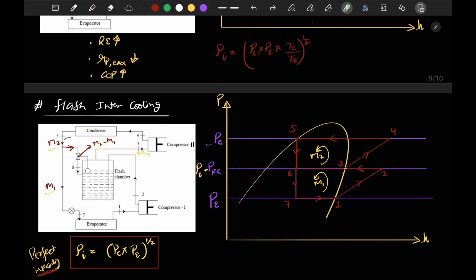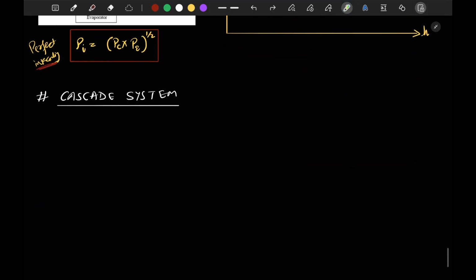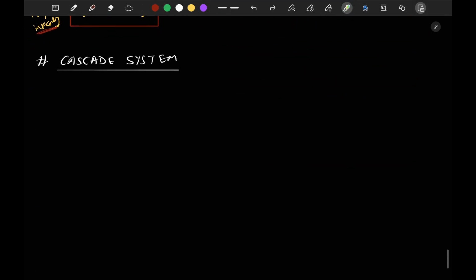Similarly, extremely low pressure in the evaporator will lead to high suction vacuum. So these are certain problems which arise in operation with a single refrigerant, in case of our high pressure issue. So for that case we use our cascade refrigeration.